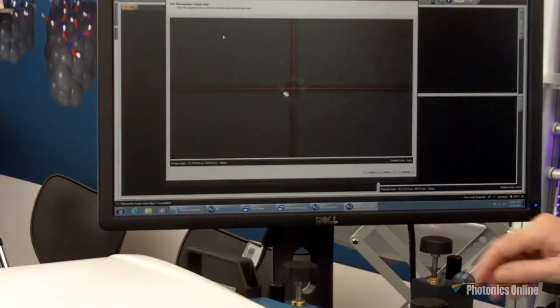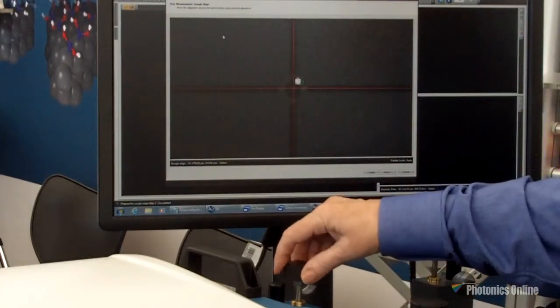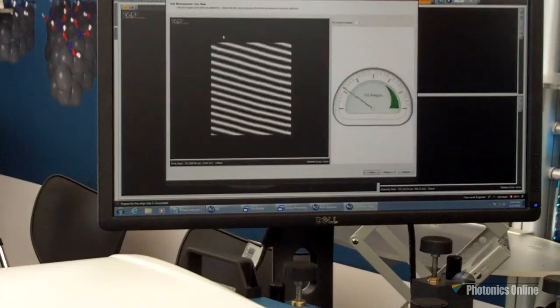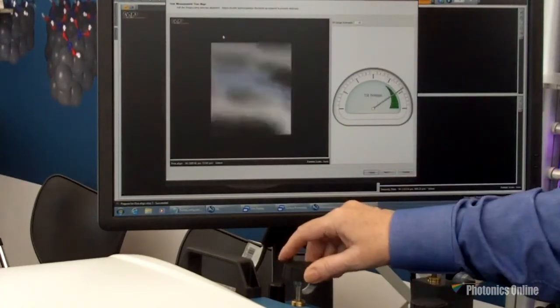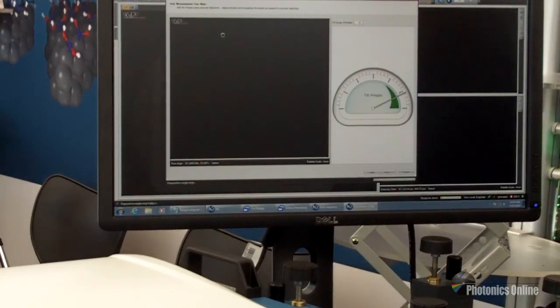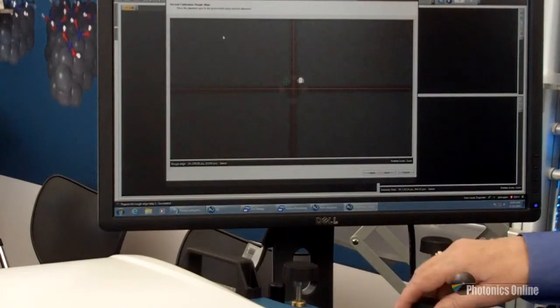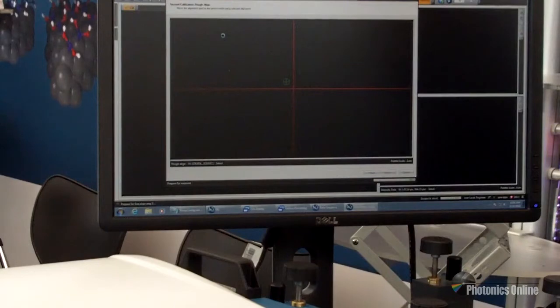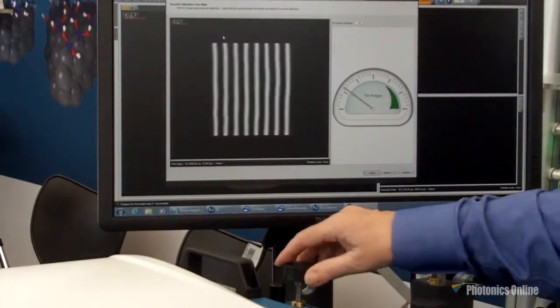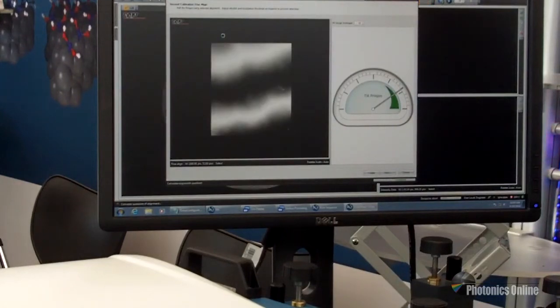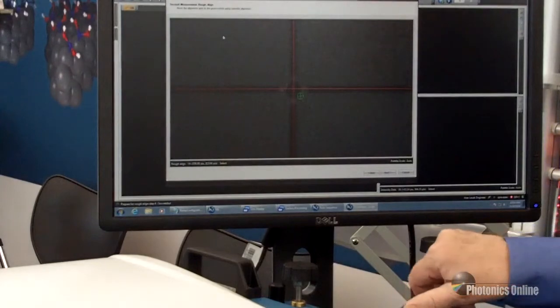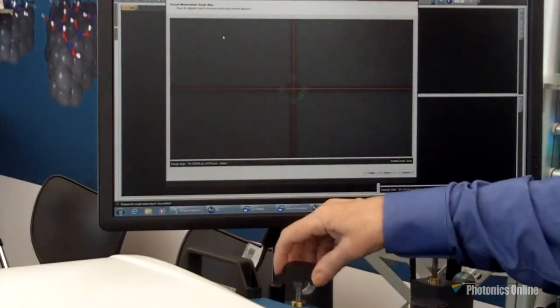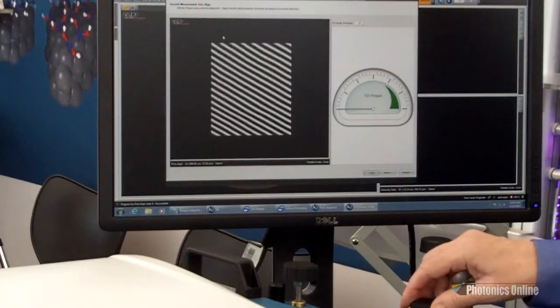To register any system error that would be normally inherent, will be calibrated out through this sequence. So I'm introducing tilt from four different directions. And doing this one time through for a given measurement situation, to effectively calibrate out any system error from my final measurement.